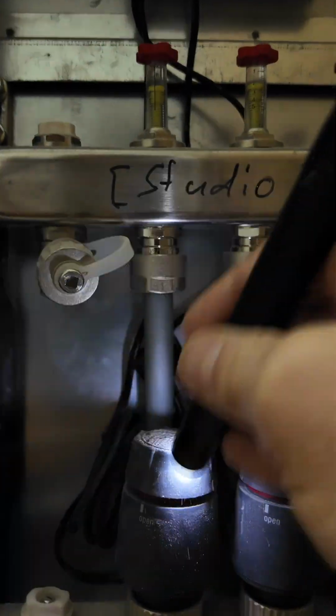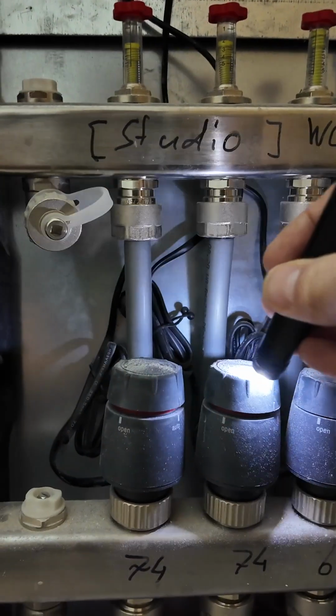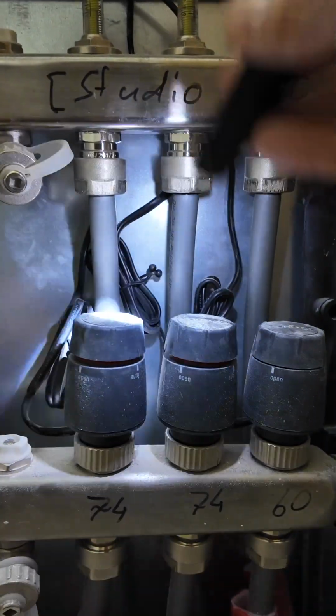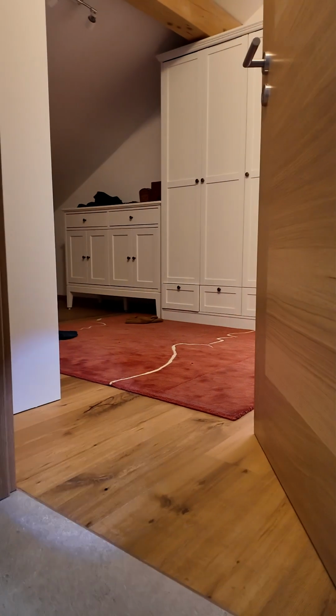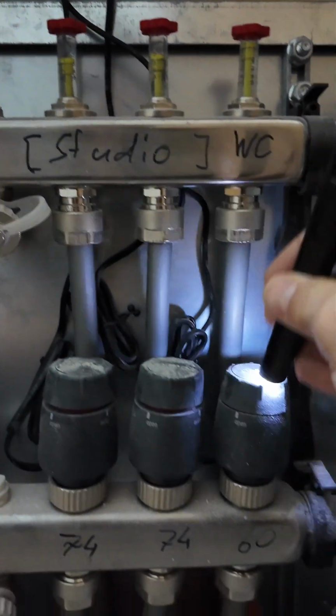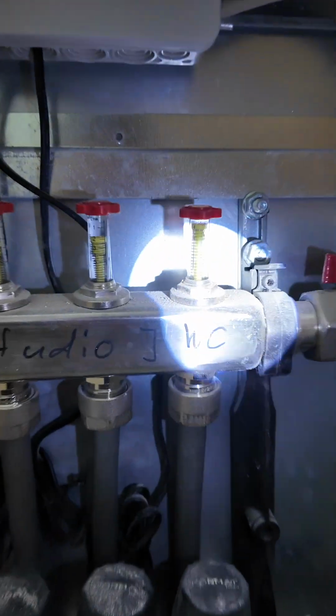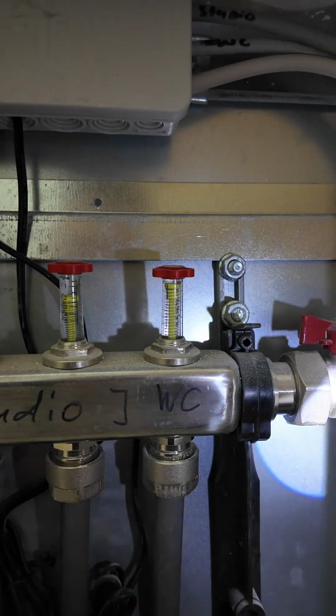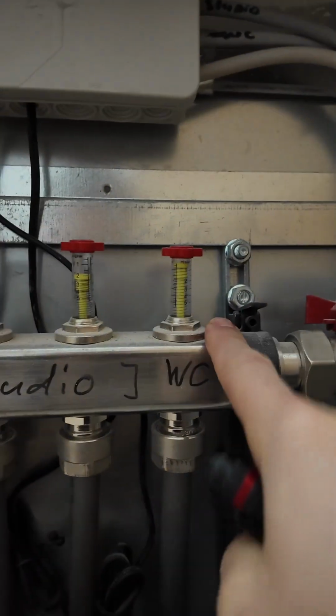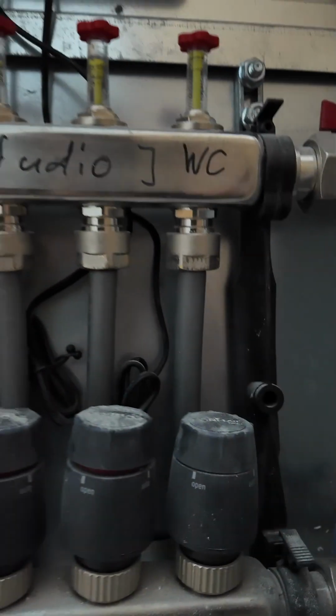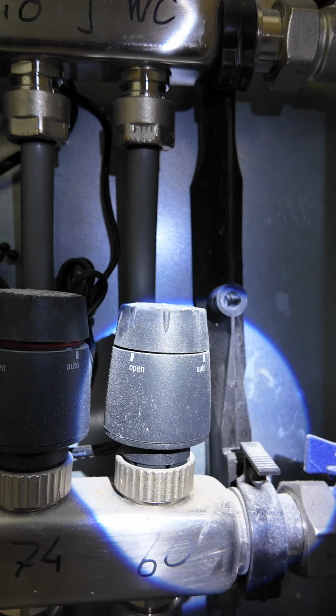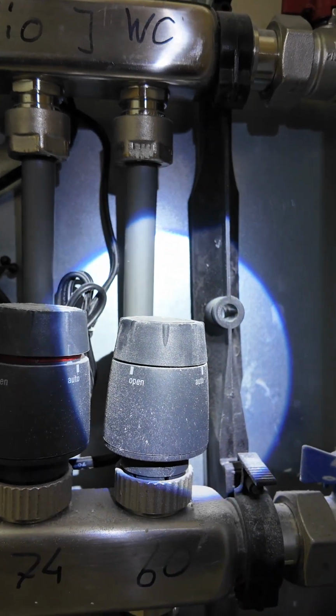So these two are actually regulating right now, or controlling the temperature of the rooms based on the thermostat, whereas this one is not. This is turned off. You can also see that the spring is all the way up on that one. So that one is for the bathroom and we got it turned off, which means that here it's also completely closed. There is no warm water flowing through there.